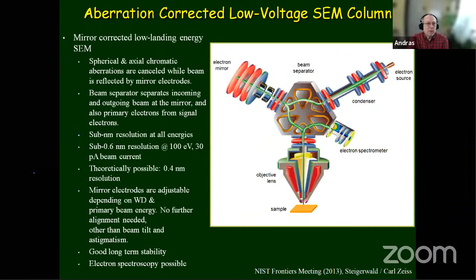If you think about it in an SEM, TEMs are similar in this regard. We throw away every electron but 1 out of a million. So the emission is in the nanoamp region, and the high resolution imaging current is in the picoamp region. But in this case, for low energy operation, they don't do that. They had to design and reconfigure the system to be able to minimize chromatic aberration this way. They use a thermally assisted electron source. So the point is that this is one of the possibilities, novel designs. Next slide, please.